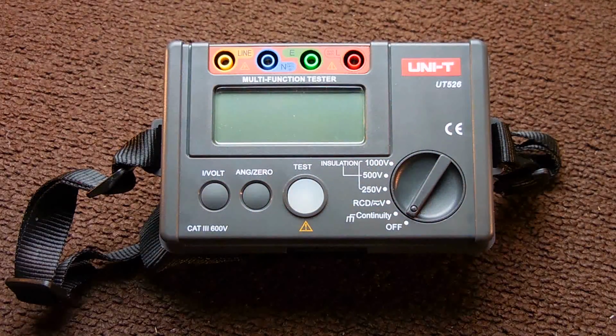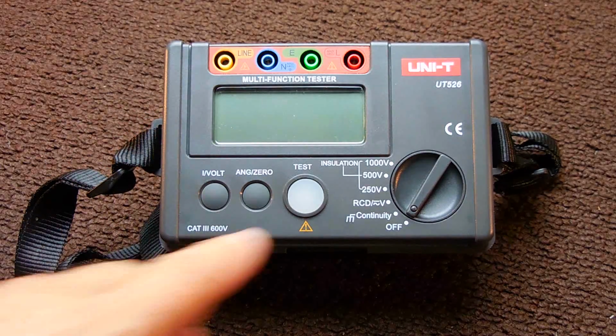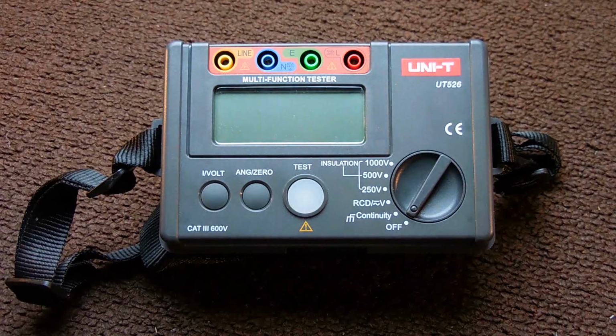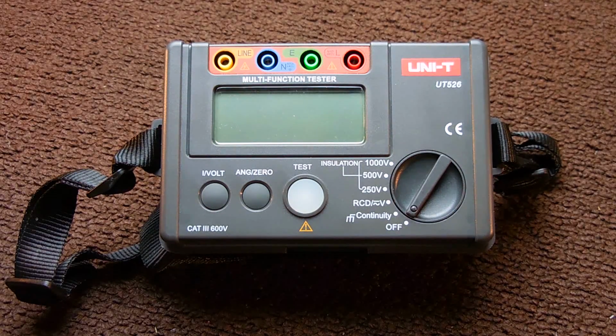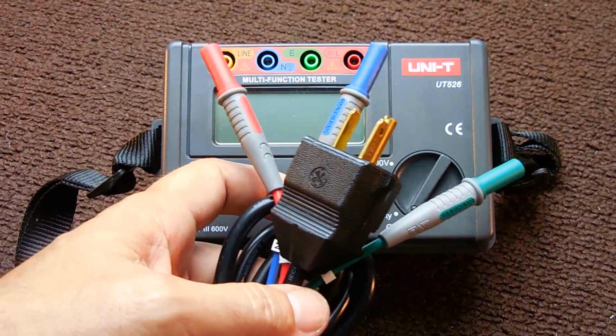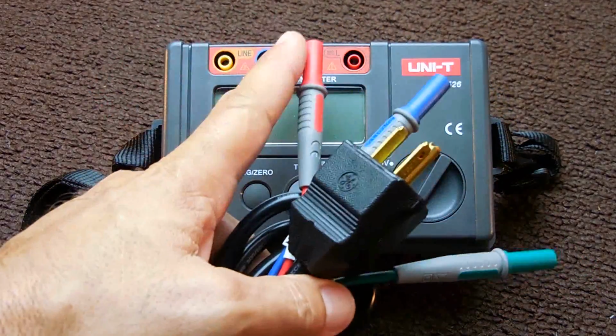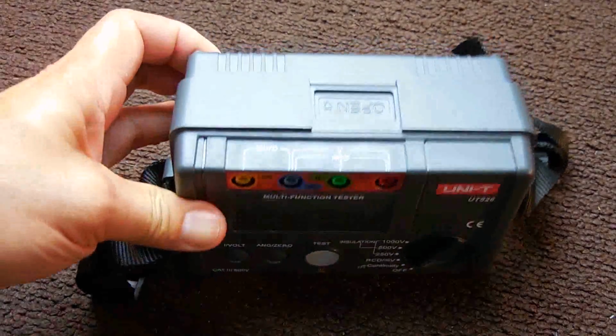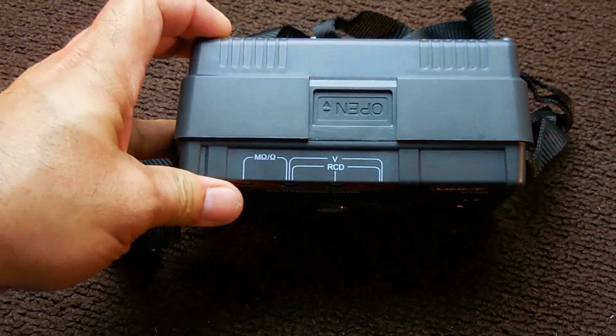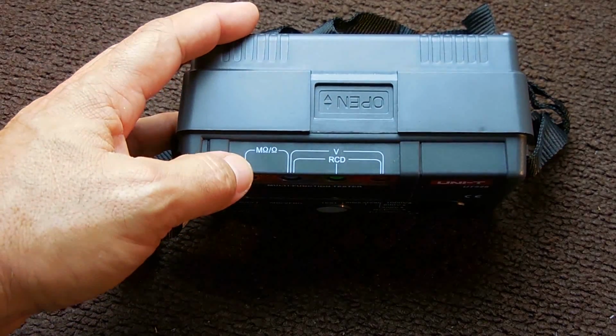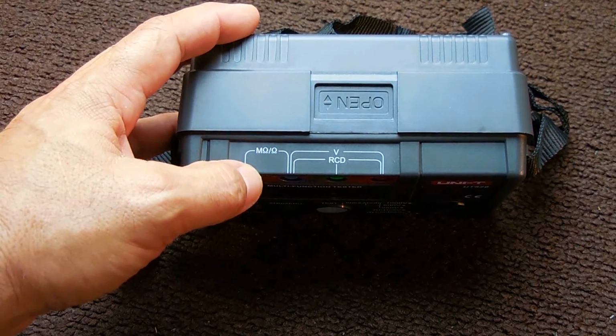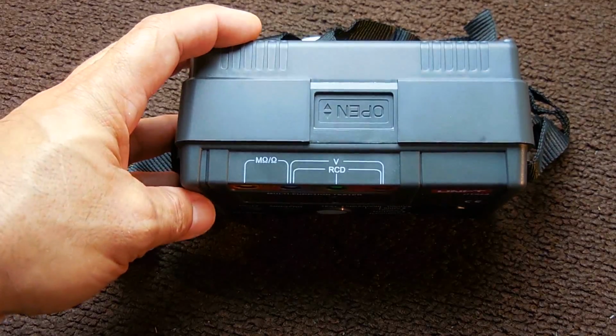Now, unlike the crank Megger, not only is this unit a lot smaller, but it does go up to 1000 volts for the insulation tests. In addition, it also tests up to 500 megohm, unlike the crank generator, which only shows a high of 100 megohm. This unit does have multiple functions, even though I only use 2 or 3 of them. You can take this cord right here, and you can plug it in right over here, blue with the blue, red with the red, green with the green, and you can take a peek at the top right here, and you can see it says RCD and V for voltage, and over here where it says megohm, ohm, that's where you're going to be connecting the test leads to measure the resistance of the insulation.